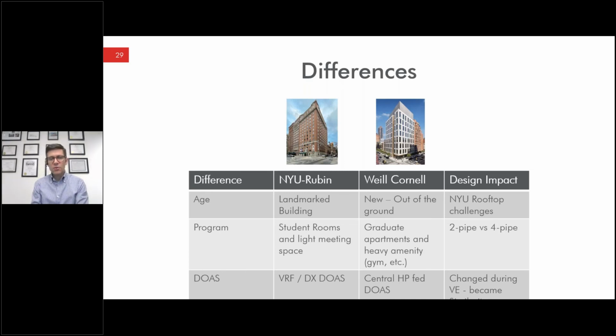The other component here that we looked at was how we condition the outdoor air at the DOAS. We looked in both buildings at a local VRF coil condition design versus a central heat pump, so glycol coils in the outside air units fed from the heat pumps. We changed that a couple times on Weill Cornell, and largely driven by cost. I'll speak about that a little bit in a second.